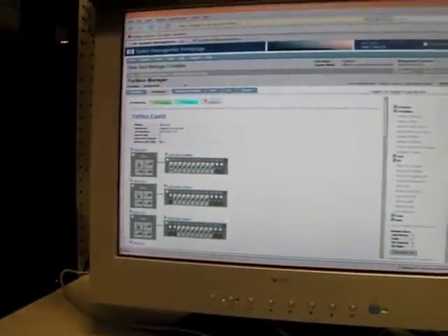But Mark went to go check on the power and cooling. When you look at the power and cooling, we get a reporting of the whole system back. So you see we got cabinet 0, cabinet 1, and then we got the 4 blowers up here, 4 blowers there. We got our I/O fans. We got our power supplies here, right? So everything's reporting back that it's okay. So 4 okay, no failed, right?